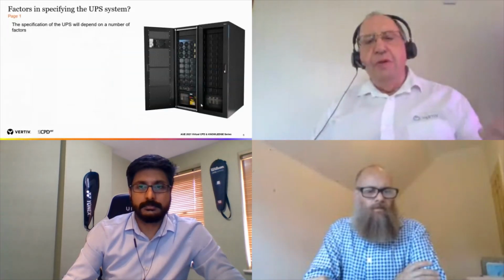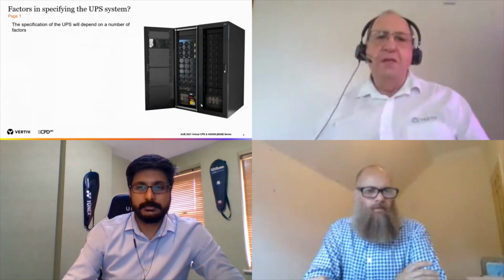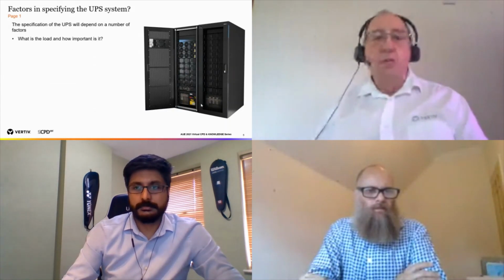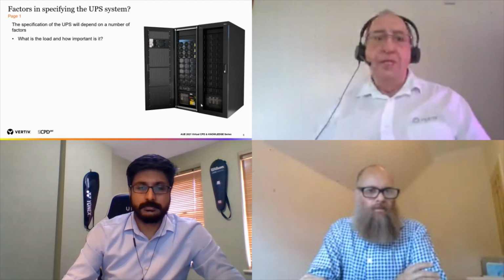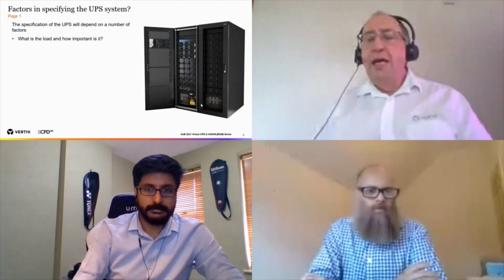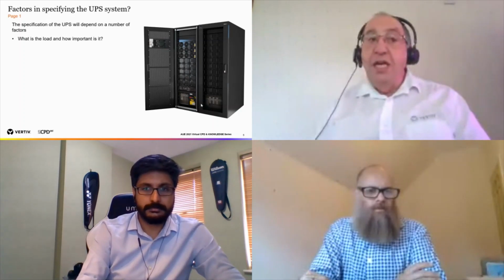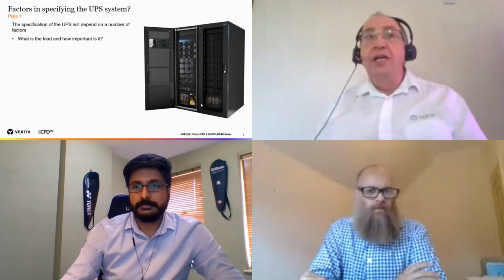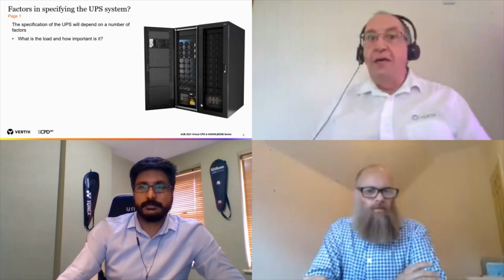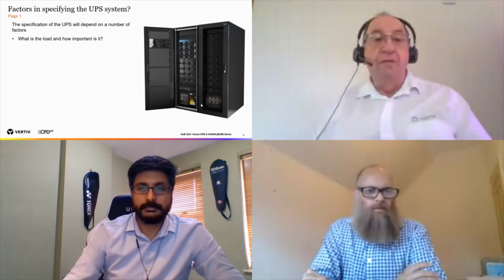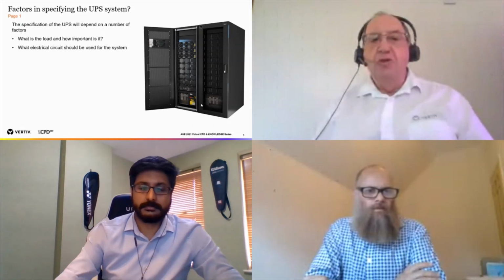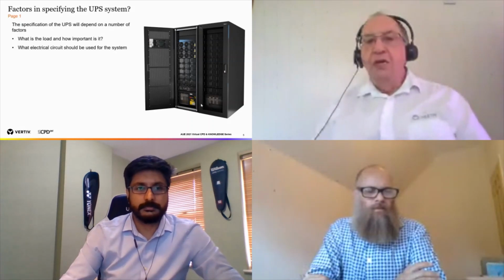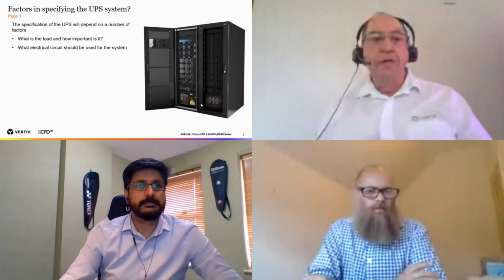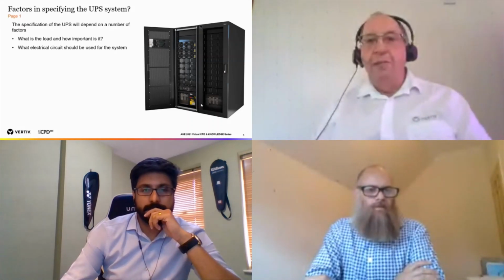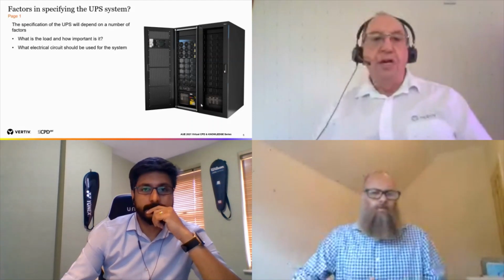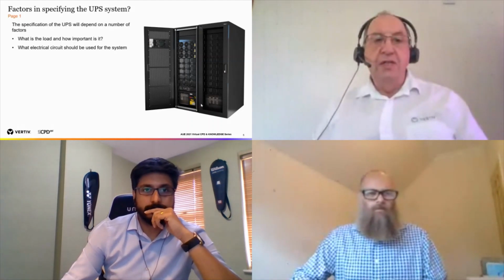So the factors that we need to consider when we're specifying UPS systems is obviously what is the load and how important is it. You know, can we have 5 minutes a year for servicing, or is 30 minutes or an hour okay for servicing a year where the UPS is going to be off? What's the electrical circuit that should be used for the system? Do we have neutral available, for example? If it's going into a foreign application, we might have a strange electrical system that we need to connect into.